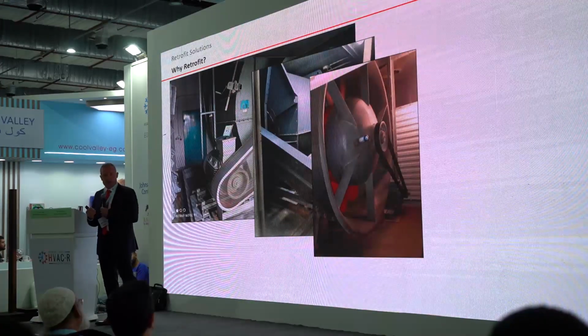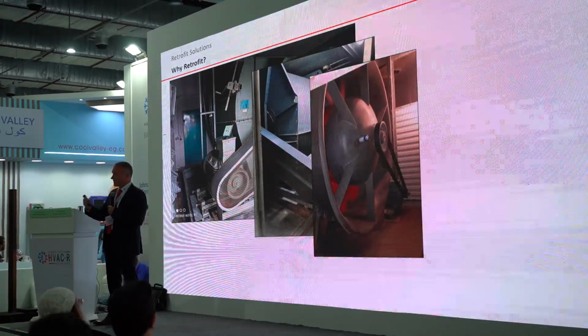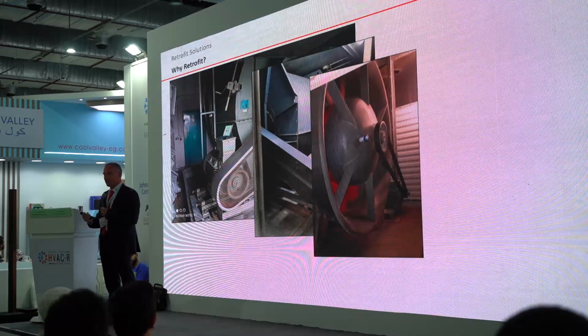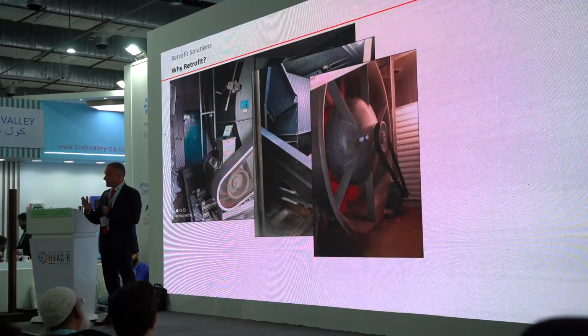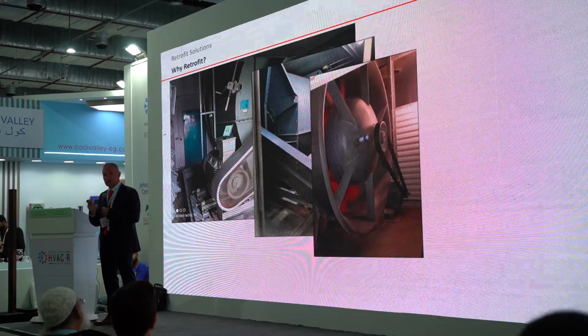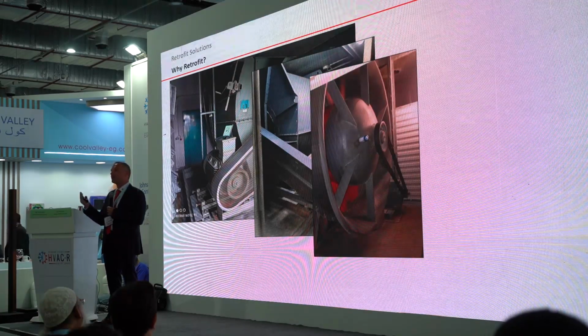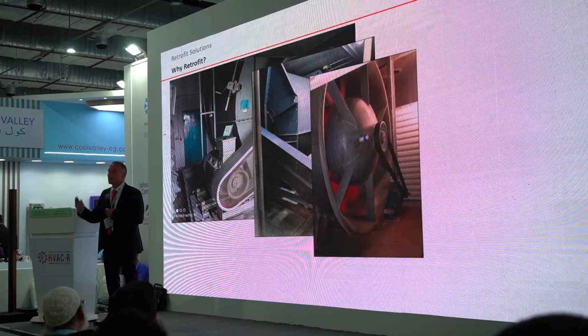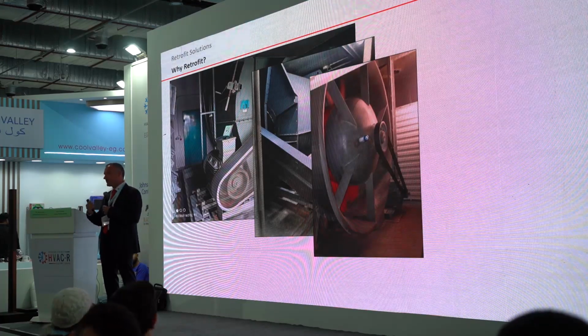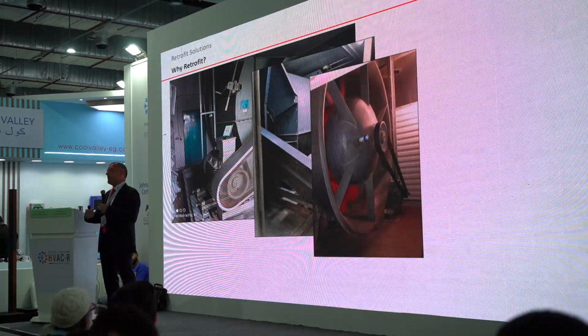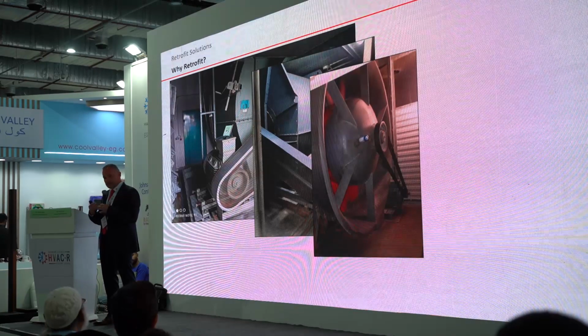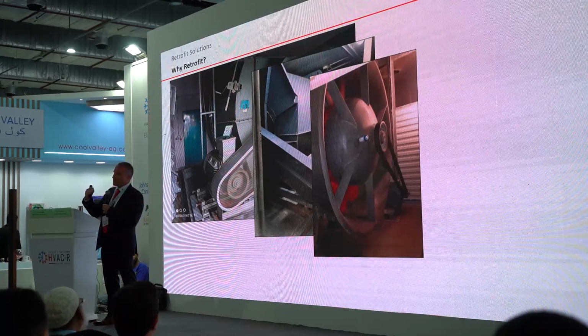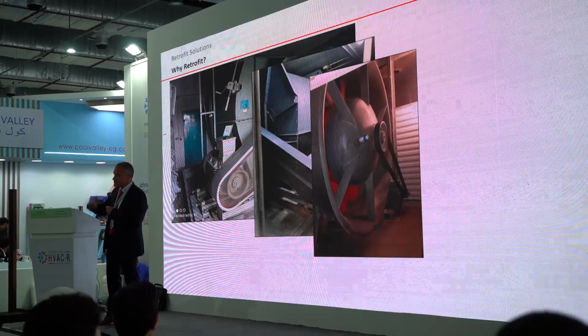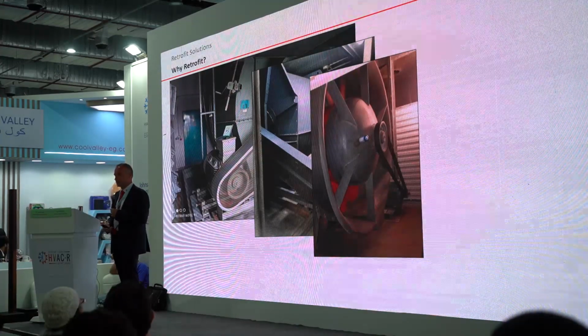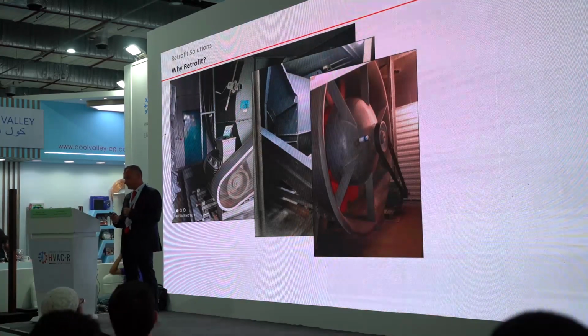So last year we went to a hospital doing an inspection of an AHU, and we saw that the fan was running originally with 3 belts. One belt had smashed off, and the other 2 belts had to carry the load. They are overloaded, creating friction between the wheels. And if it is creating friction, the energy consumption is going up because the efficiency is going down and the whole system is not running in a good condition.